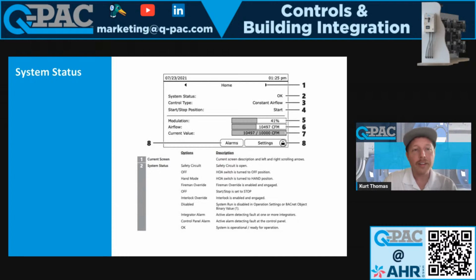All right, system status. System status is super underrated in my opinion. So whenever you're doing a startup or whenever you have an issue, this is the first thing I check. Whenever I was running technical support, this is the first thing I would ask. What's the system status say? So it's just a really quick way to diagnose what's going on with the system. It'll tell you your safety circuit's tripped. Maybe your HOA is in the off position. You're in hand mode. Fireman Override. It'll tell you whatever mode you're in will be displayed there on the HMI. It's also displayed via BACnet. So I always look at this first.